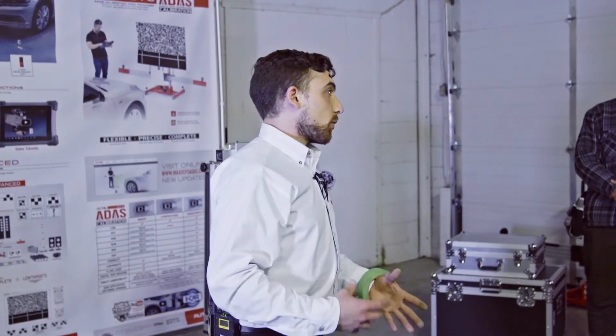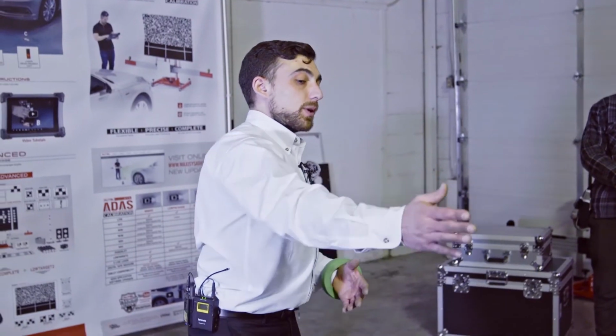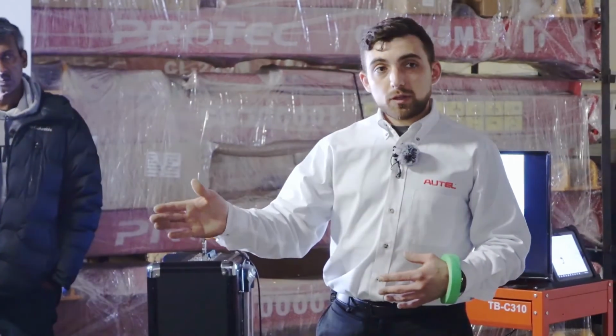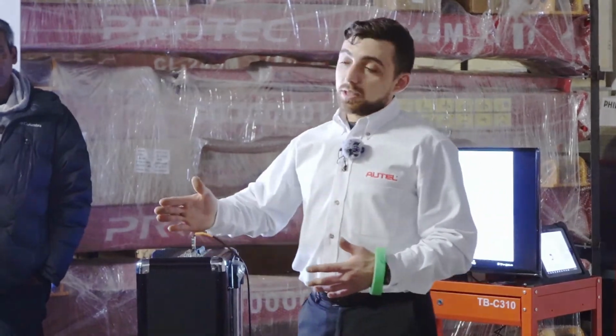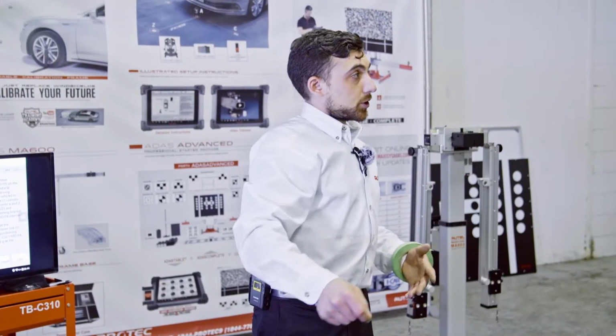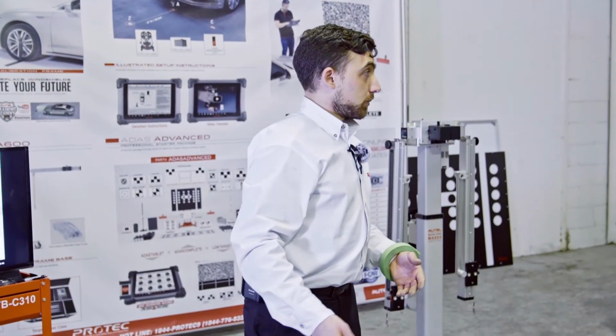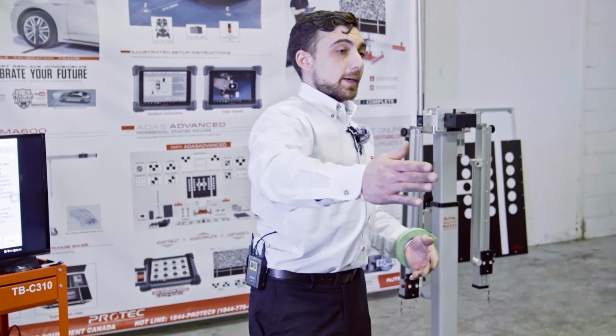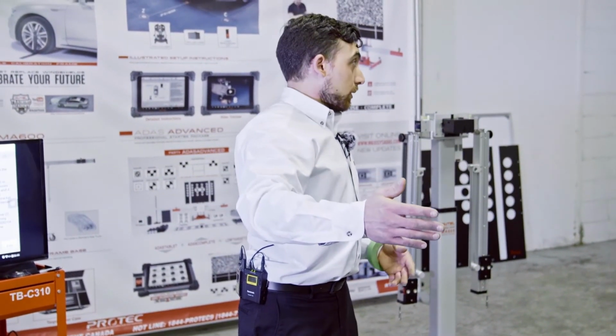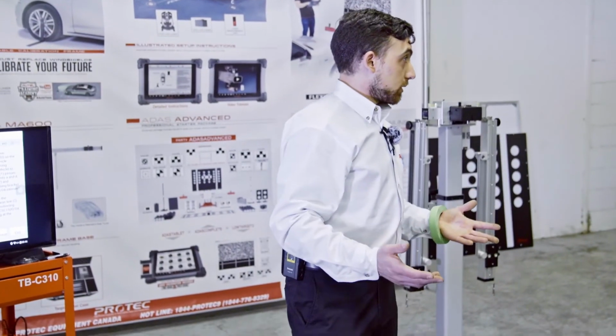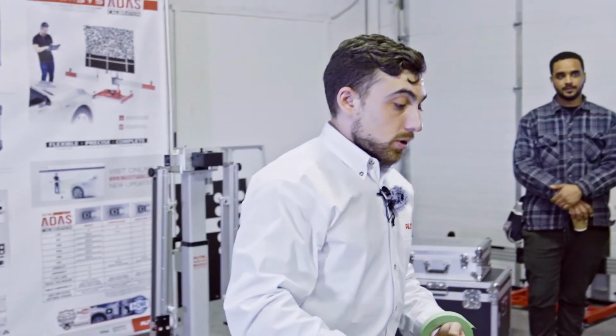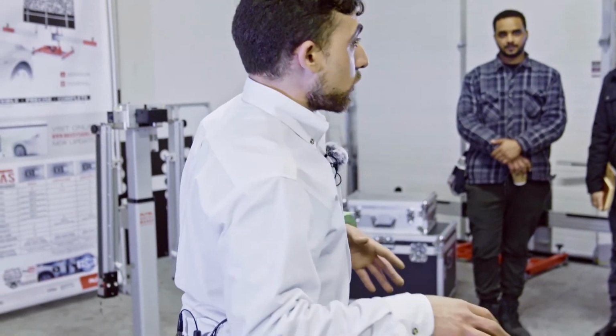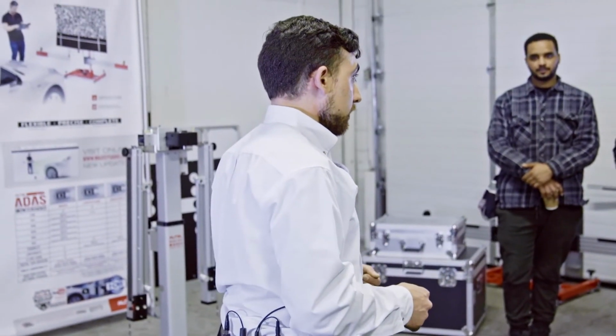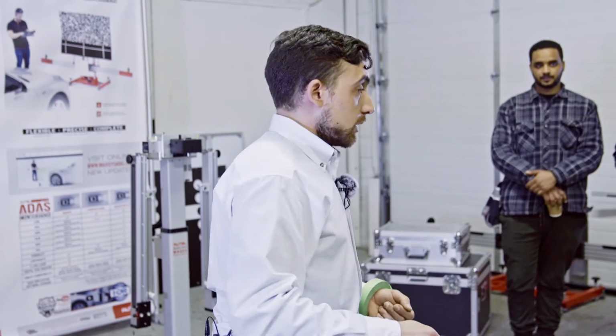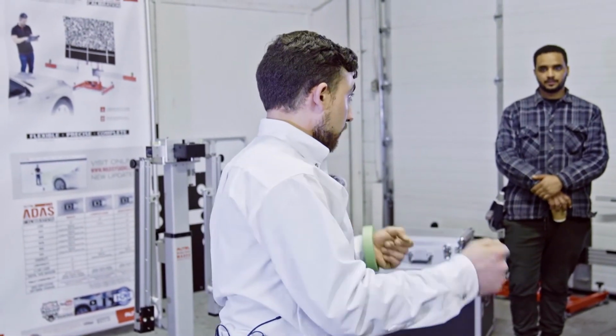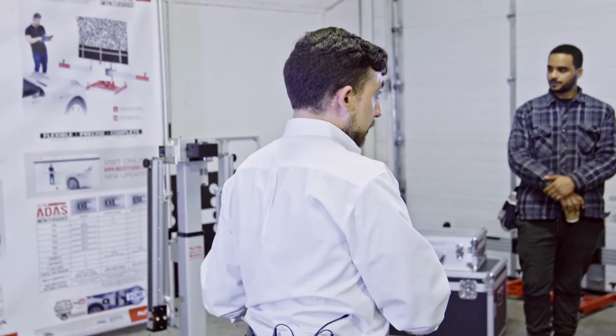The reason why we go through all this trouble is because when we're measuring our distance, if we're not perfectly straight, if let's say we're off at an angle, that measurement actually becomes longer than it should be. So if I'm straight here at 1 meter, at an angle I might be 1.1 meter, and that's off by 10 centimeters. Obviously that's a big difference. So again, the MA600, a lot more setup in order to place it properly, but once we have all these points on the ground, it's one step from this to calibration.